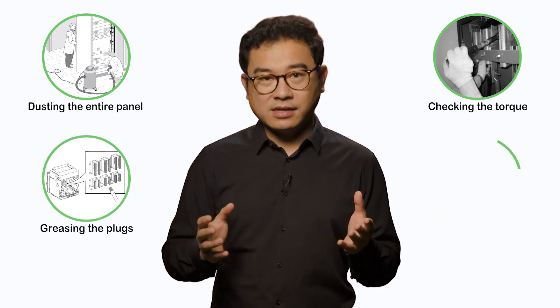So there you are. Peter and Carlos are now both project collaborators in Facility Expert. And just like Fiona at Valentino's Chocolate Factory, they are also notified 30 days in advance of scheduled maintenance. This next notification relates to MasterPact MTZ and Okken Switchboard Advanced Maintenance. Over time, dozens of specific checkups will be required — for example, dusting the entire switchboard, checking the torque of power connections, greasing the plugs, and testing of circuit breaker protection functions. As soon as I receive this notification alert, I contact Carlos and agree with him that I will offer the required services, because everything is in my domain of expertise. Then I get in touch with Fiona to schedule a service appointment.